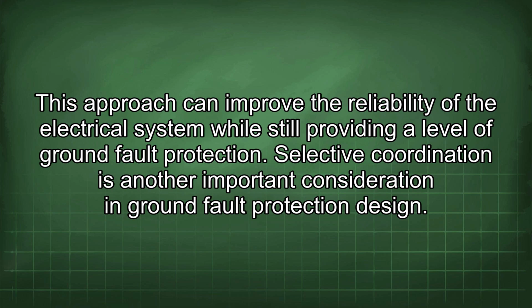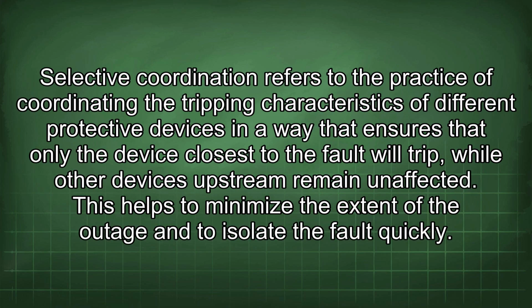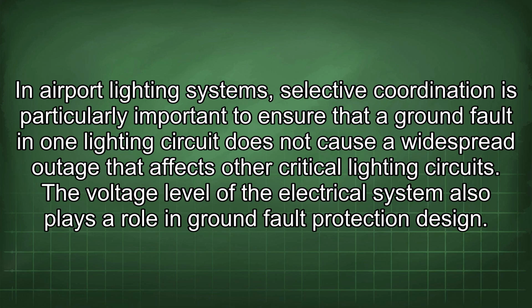Selective coordination is another important consideration in ground fault protection design. Selective coordination refers to the practice of coordinating the tripping characteristics of different protective devices in a way that ensures that only the device closest to the fault will trip, while other devices upstream remain unaffected. This helps to minimize the extent of the outage and to isolate the fault quickly. In airport lighting systems, selective coordination is particularly important to ensure that a ground fault in one lighting circuit does not cause a widespread outage that affects other critical lighting circuits.